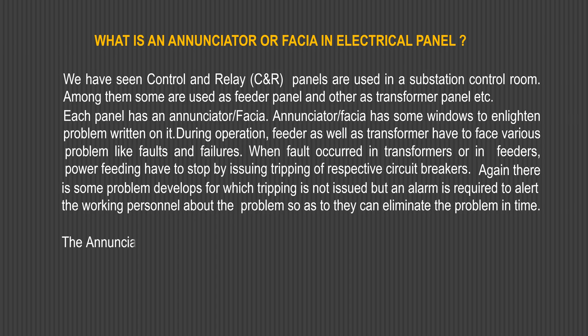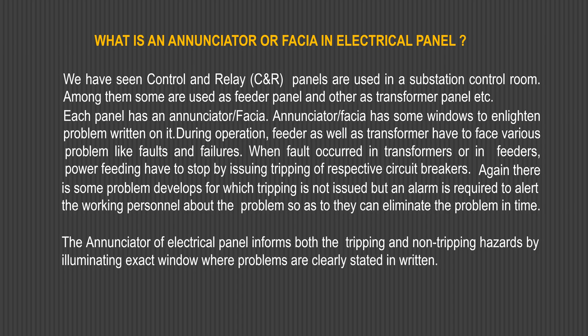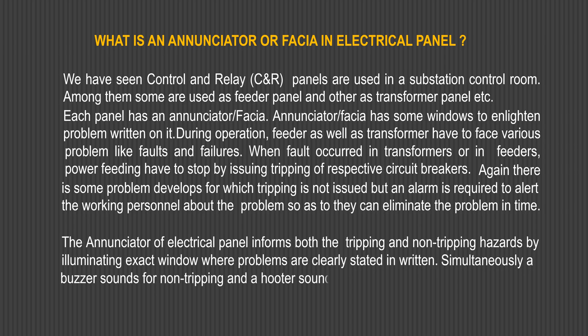The annunciator of the electrical panel informs both tripping and non-tripping hazards by illuminating the exact window where the problem is clearly stated in writing. Simultaneously, a buzzer sounds for non-tripping alerts and a hooter sounds for tripping alerts. Working personnel first accept the sound and then take necessary action by steps.